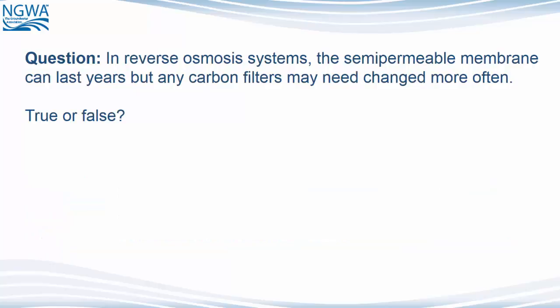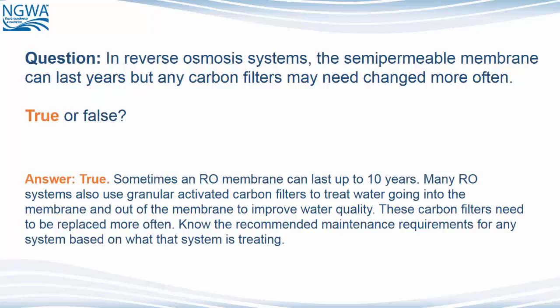Question: In reverse osmosis systems, the semi-permeable membrane can last for years, but any carbon filters may need to be changed more often. True or false? The answer is true. Sometimes an RO membrane can last for up to 10 years. Many RO systems also use granular activated carbon filters to treat water going into and out of the membrane to improve water quality. These carbon filters may need to be replaced more often. Know the recommended maintenance requirements for any system based on what that system is treating.